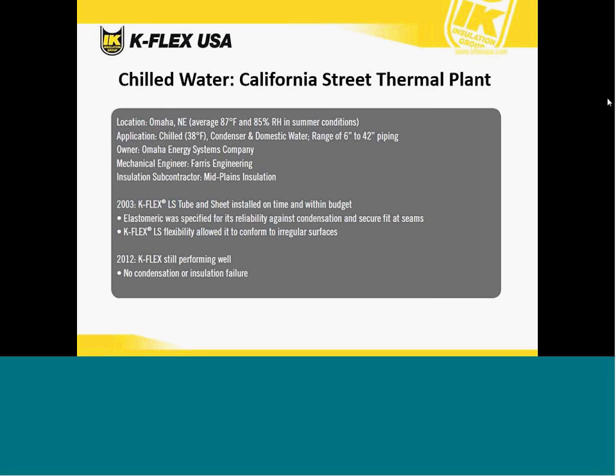It was installed in 2003 with K-Flex LS tube and sheet. Elastomeric was specified because of its reliability against condensation and its secure fitted seams. We went out in 2012 and performed an inspection. We found no evidence of condensation or insulation failure.